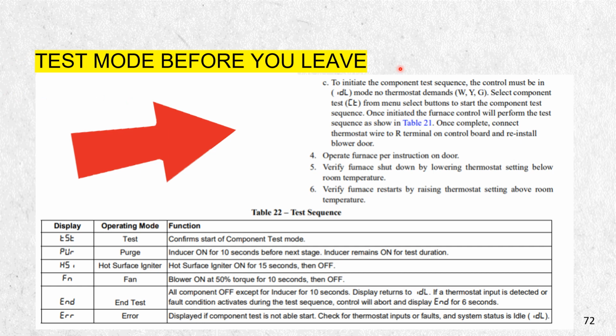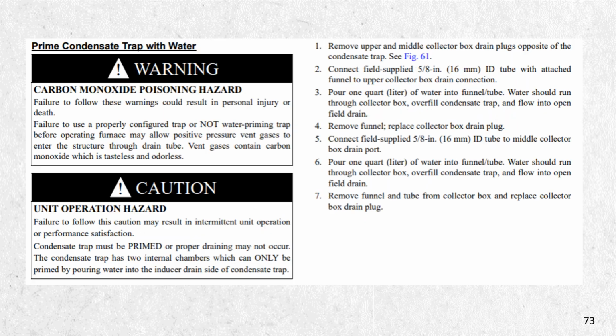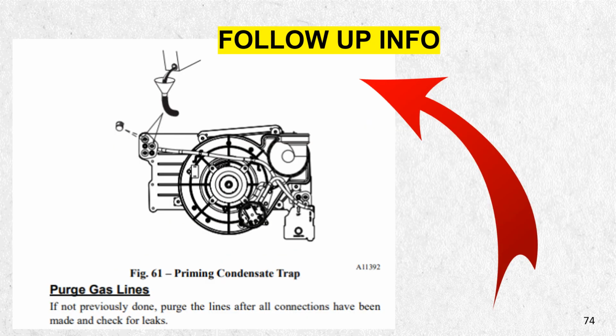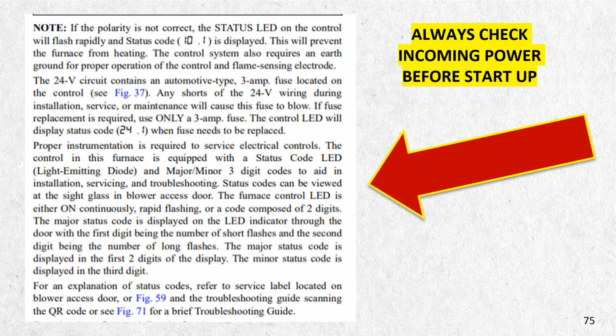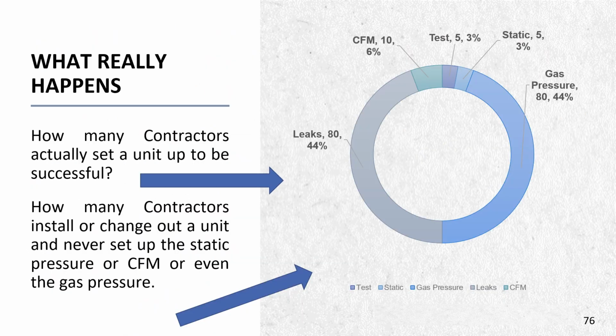Make sure you have all that set up. And then this is test mode before you leave. Once you get it installed, you go through its steps. Run the test mode. It'll tell you what all you need. Purge the lines. It'll check the igniter coming on. The fan will come on. Then it'll end the test and go back into idle mode. And then don't forget to prime your condensate trap with water. Make sure you got all that done. And then, like I said, you're looking at this.